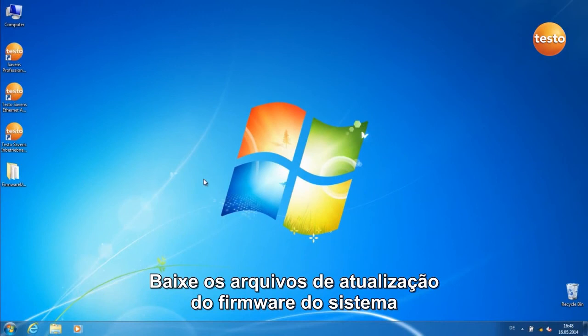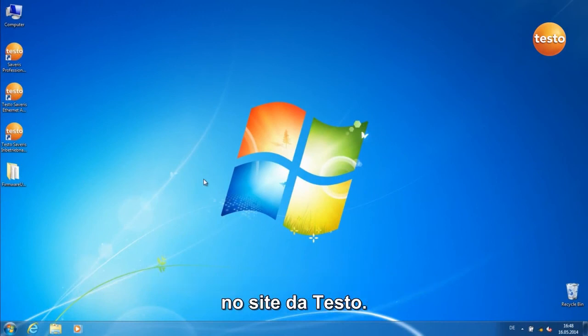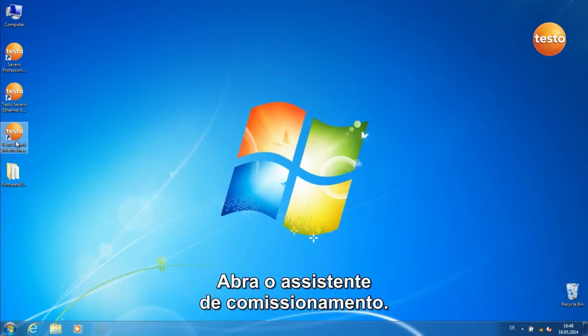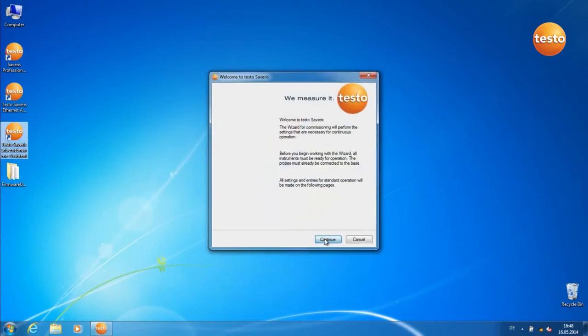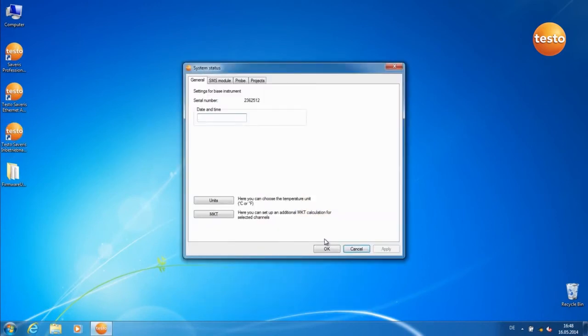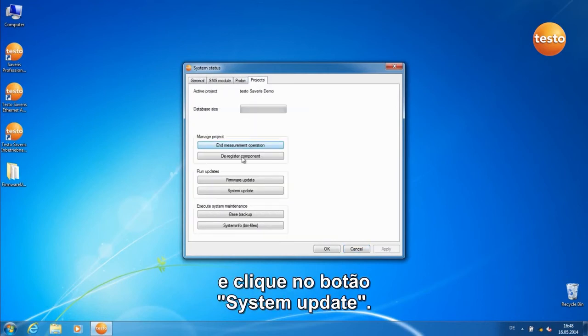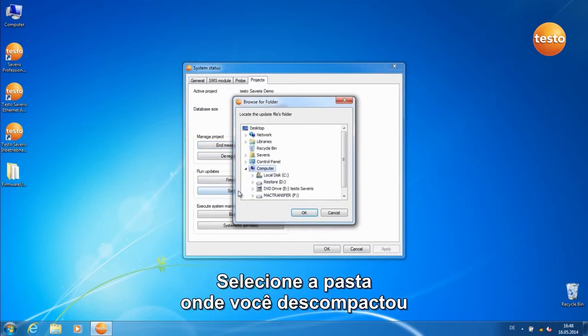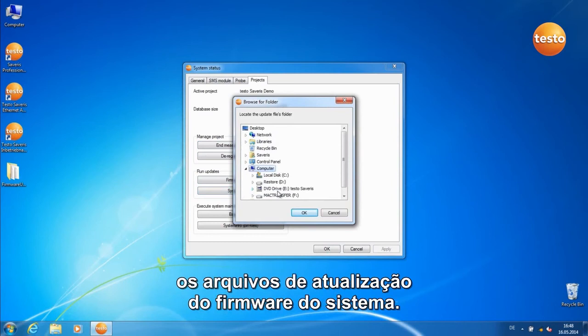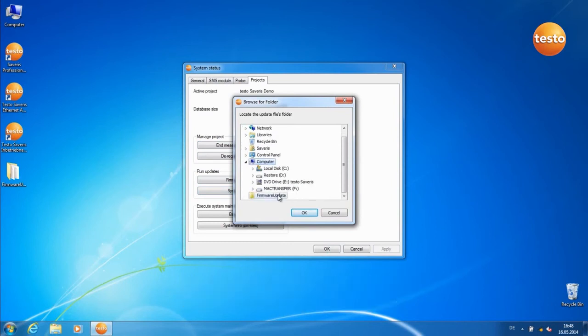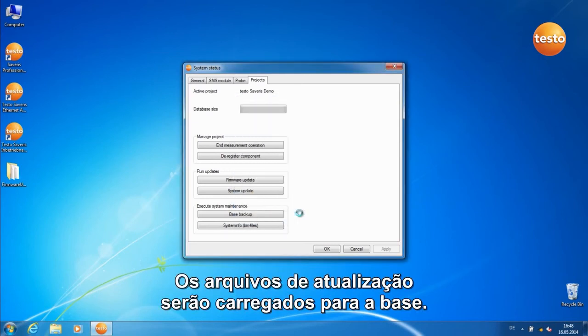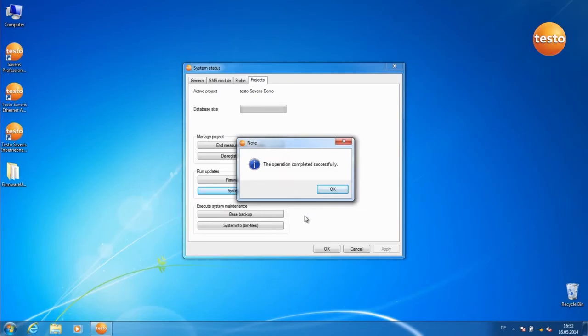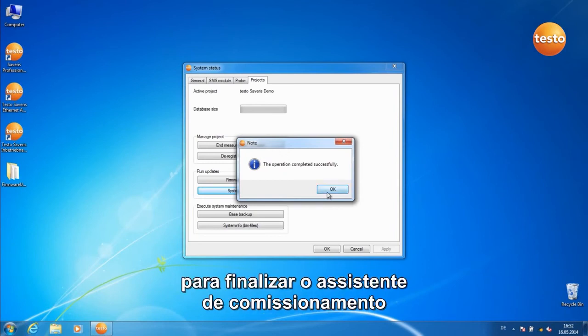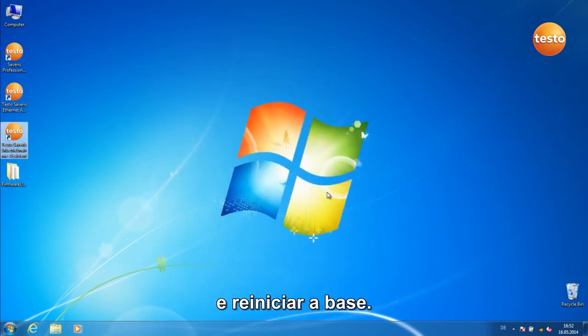Download the firmware system update files from the Testo website. Open the Commissioning Assistant. Go to the tab Projects and click on the button System Update. Select the folder where you've unpacked the firmware system update files. Click on OK. The update files are now loaded into the base. Click on OK to end the Commissioning Assistant and restart the base.